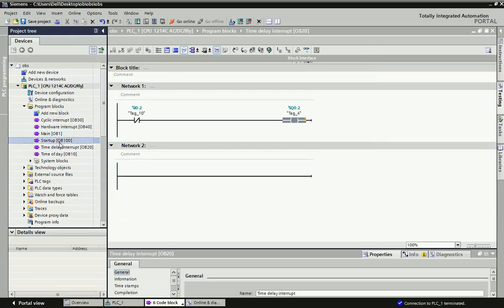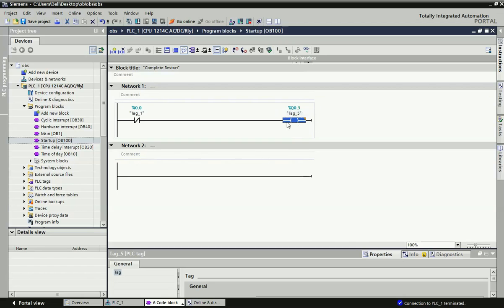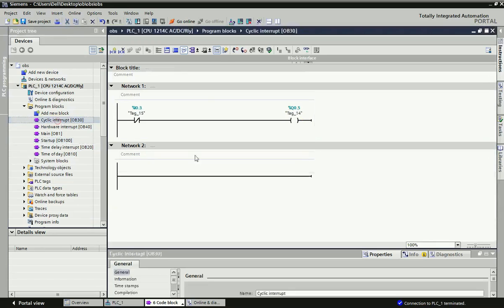Here I have used startup OB100, also called warm restart. There is an NC contact and output Q0.3. When I change the state from Stop to Run mode, it will execute only once and Q0.3 will turn ON. After that, even if I trigger input I0.0, there will be no impact on Q0.3 — this output will remain continuously ON after changing from Stop to Run mode.